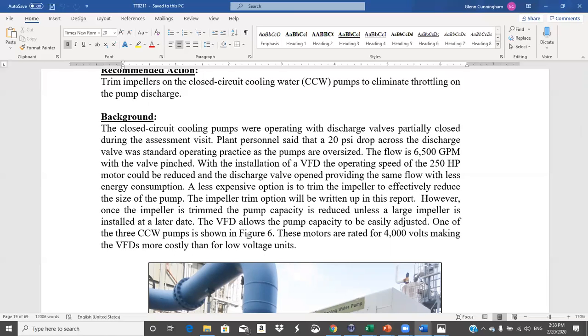Today that would probably be purchased with a VFD. If you have a VFD, you don't have to use the valve. Go ahead and oversize it a little, but put your flow meter on it, figure out what you need, adjust the speed, lock it down, and you're good to go, or put an automatic control on it. This valve control is a thing of the past, but the whole world has been built that way for years. So you go to work for somebody, they're not going to have all brand new equipment. You're going to walk in and see something three times older than you are, and they expect you to work on it.